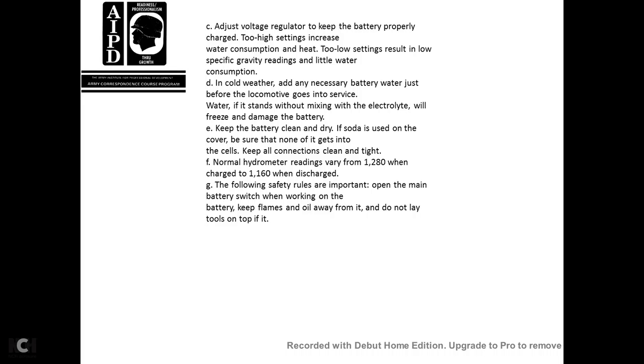D. In cold weather, add necessary battery water just before the locomotive goes into service. Water standing without mixing with the electrolyte will freeze and damage the battery. E. Keep the battery clean and dry. If soda is used on the cover, be sure that none of it gets in the cells. Keep all connections clean and tight. Normal hydrometer readings vary from 1,280 when charged to 1,160 when discharged. The following safety rules are important. Open the main battery switch when working on the battery. Keep flames away, keep oil away from it, and do not lay tools on top of it.